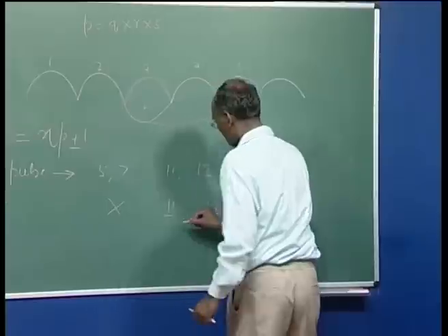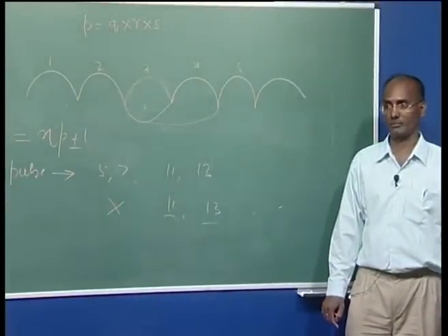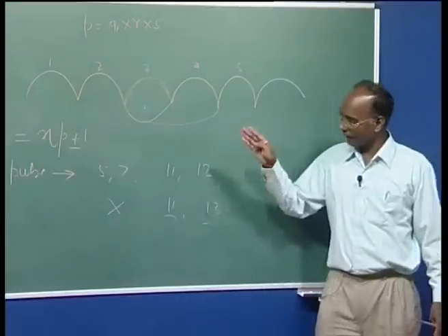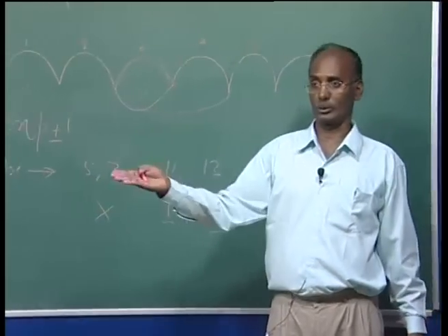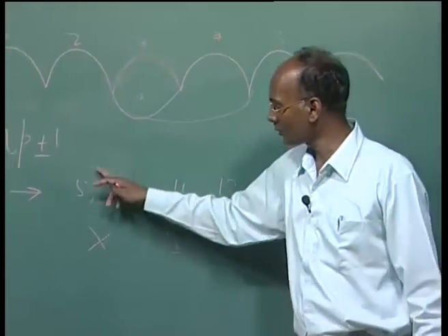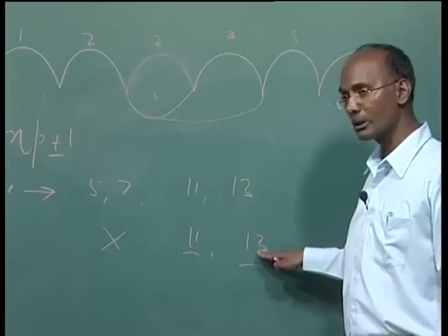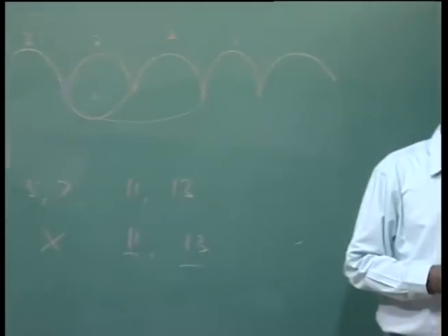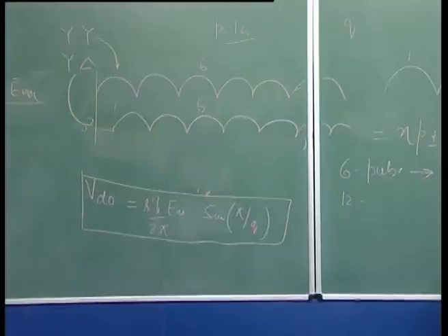So you can see that some harmonic components are eliminated automatically with this configuration. Also, these lower harmonic components have the higher magnitude, and we will analyze that the magnitude of this harmonic current is larger compared to the others. So the magnitude is also reduced, and some are cancelled, in 12 pulse operation, which is normally used in HVDC links. This 12 pulse operation is nothing but 6 pulse operation with two transformers connected in series on the secondary side.